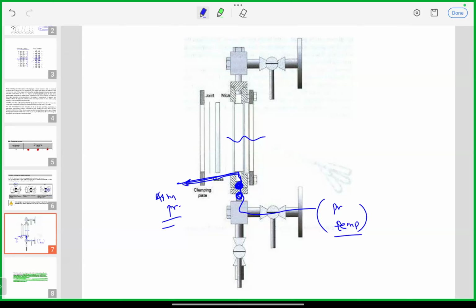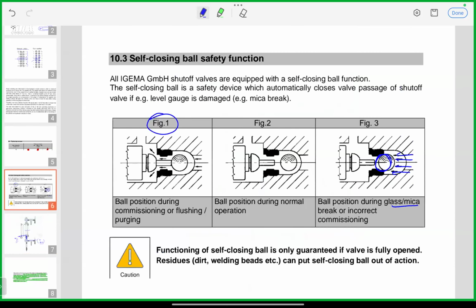And that can be a serious safety hazard. It can cause severe injuries to the person operating around the boiler, or it can even cause damage to surrounding machineries as well. So to enhance safety, gauge glasses are required to be provided with this steel ball on the water side, which is called the self-closing ball.